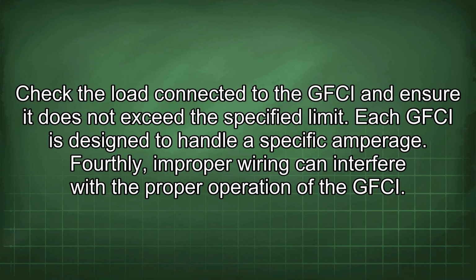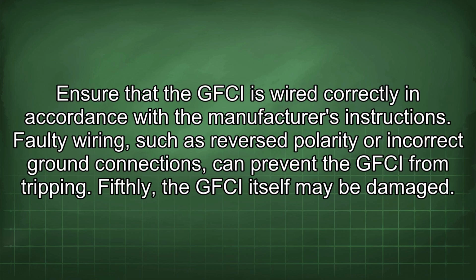Fourthly, improper wiring can interfere with the proper operation of the GFCI. Ensure that the GFCI is wired correctly in accordance with the manufacturer's instructions. Faulty wiring, such as reverse polarity or incorrect ground connections, can prevent the GFCI from tripping.